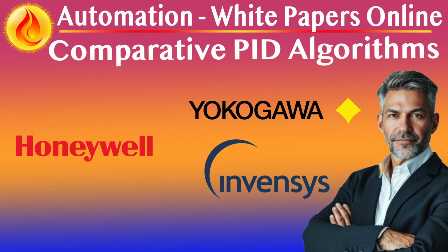Derivative handling and noise management. Derivative action is where Yokogawa excels in configurability. It supports derivative on PV only as a default, enables explicit PV filtering with adjustable time constants, and separates D-action filtering from signal filtering, offering layered protection against noise.